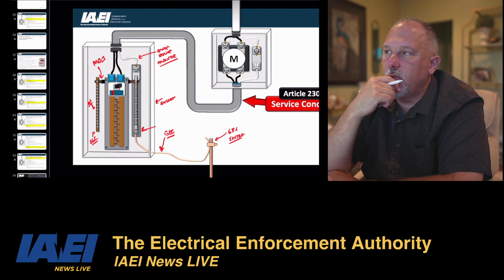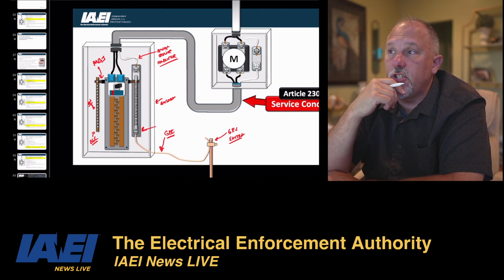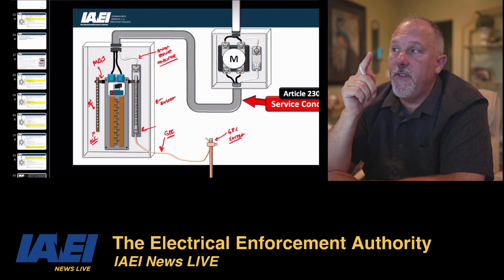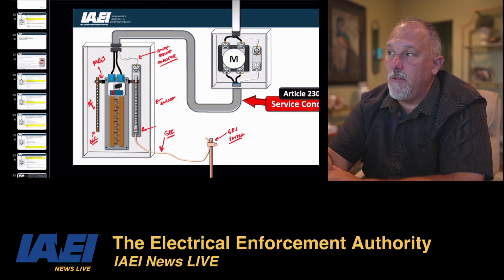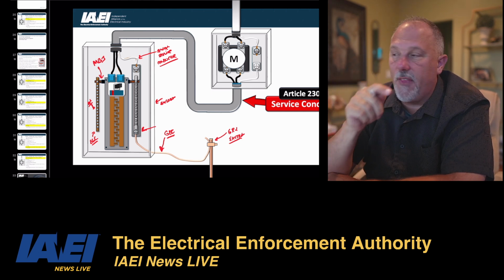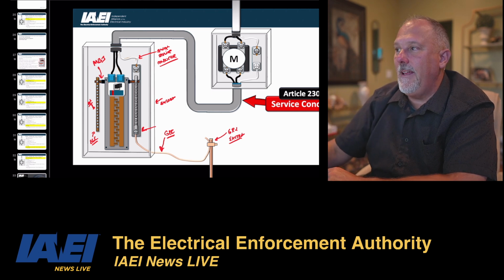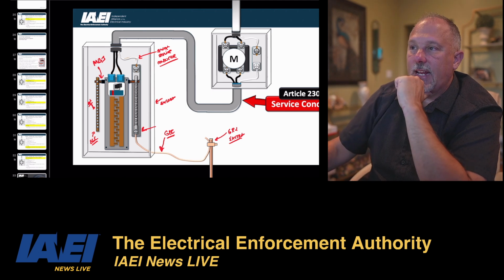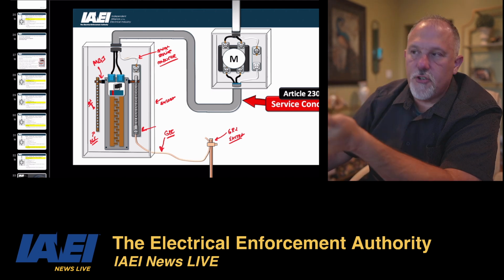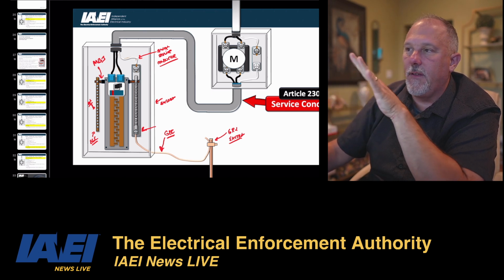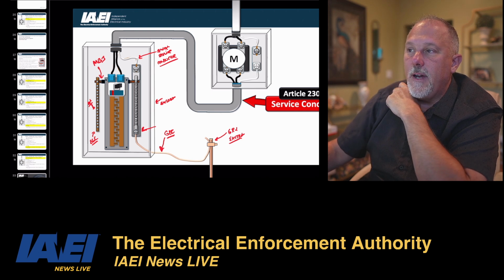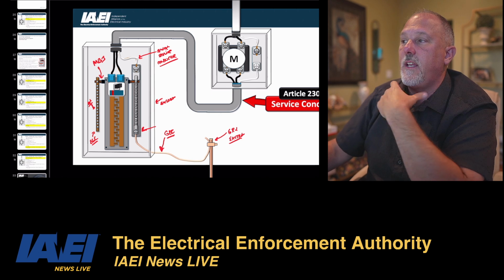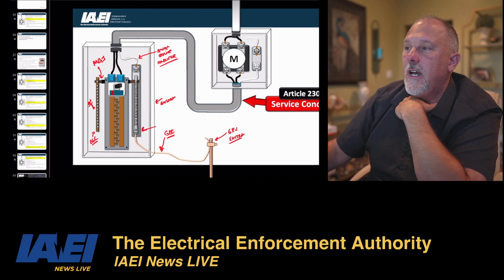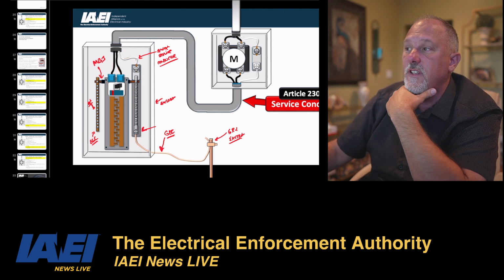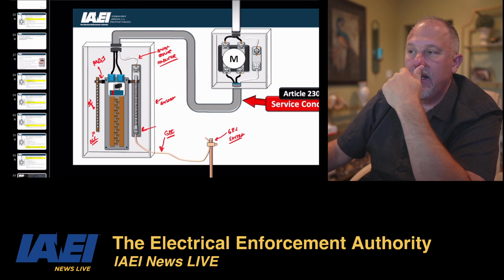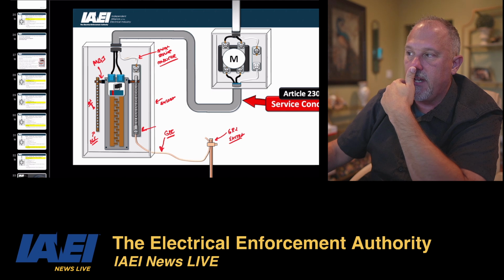Electrical continuity of the service equipment, service raceways, and service conductor enclosures shall be ensured by one or more of the following methods. Bonding equipment to the grounded service conductor by an applicable method, 250.8(A). And 250.8(A), remember, we already talked about that. Listed pressure connectors, your terminal bars, exothermic, all that good stuff. Connections made up wrench tight using threaded couplings, threaded entries. Threadless couplings and connectors if made up tight for metal raceways. Other listed devices such as bonding type locknuts, etc.